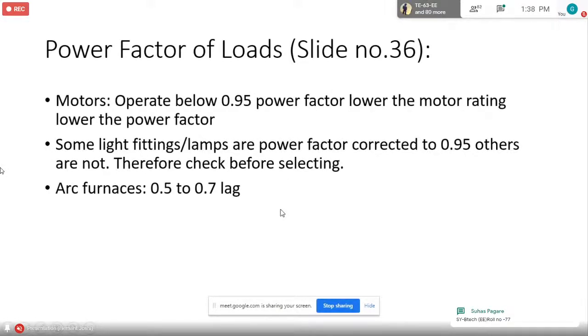Motors operate below 0.95 power factor; the lower the motor rating in kilowatts, the lower the power factor. Roughly, I would say any motor from 100 kilowatt and above will definitely have 0.92 or better power factor. Some light fittings and lamps are power factor corrected to 0.95, others are not. Therefore, check before selecting. Arc furnace is 0.5 to 0.7 lag. Arc furnace is very, very horrible.